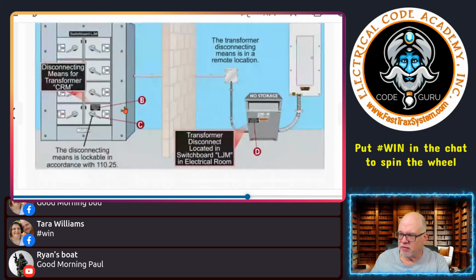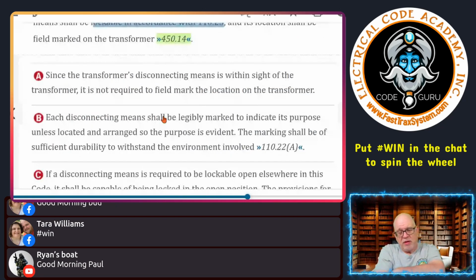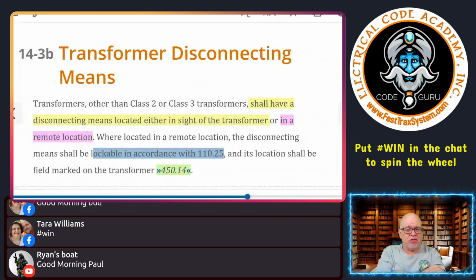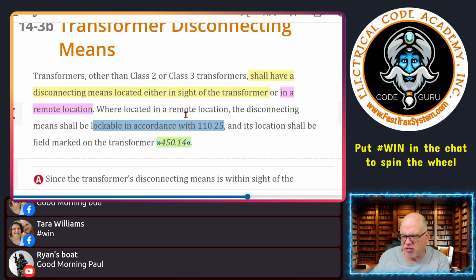So we covered most of everything. That's our disconnect requirements. If you're installing a transformer and it's just the disconnecting means, that's all, then you have to make sure it is installed either within sight of the transformer, or if it's remote, it has to have the labeling and all that. Now, remember, with transformers it would hardly ever be just a disconnect. It's also going to have fuses or circuit breakers in it, whatever is also providing the protection to the transformer. I wouldn't waste my money putting in a disconnect and not providing adequate protection for the transformer or even what's necessary for the conductors. That seems like adding stuff that's just a waste of money. So just keep that in mind.